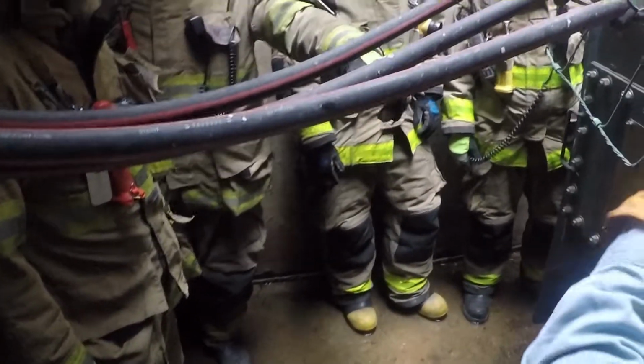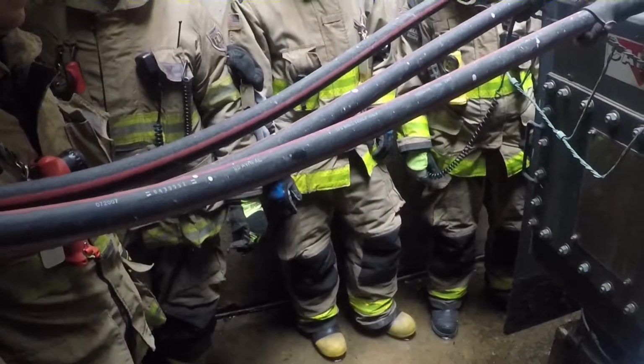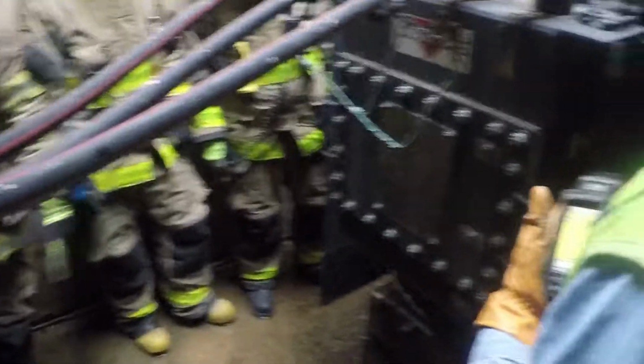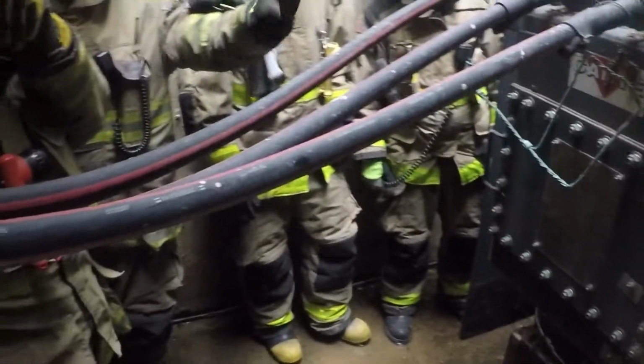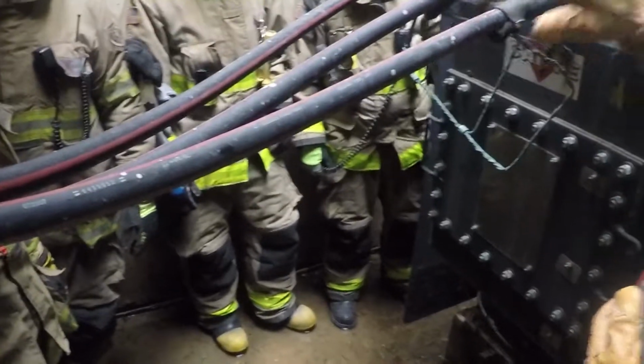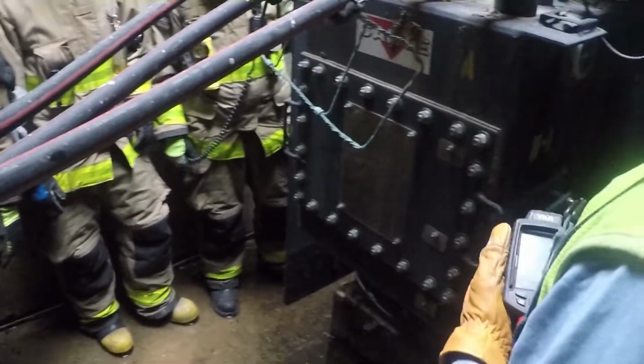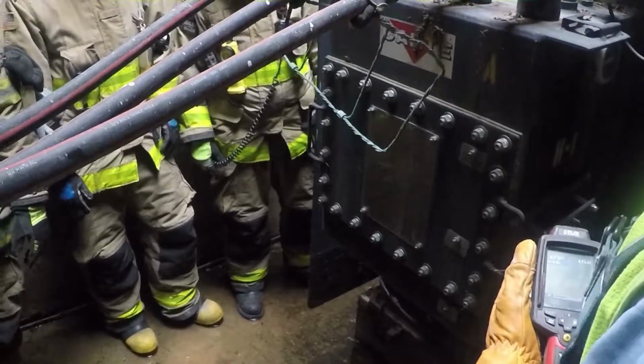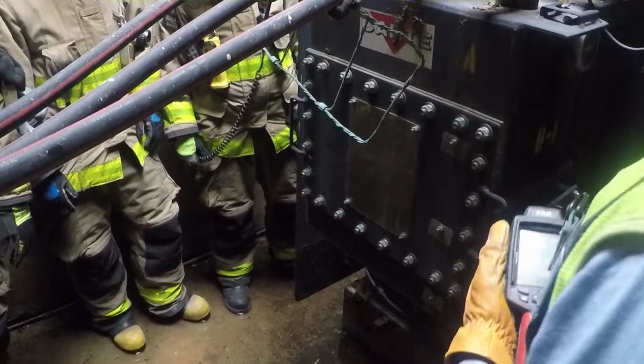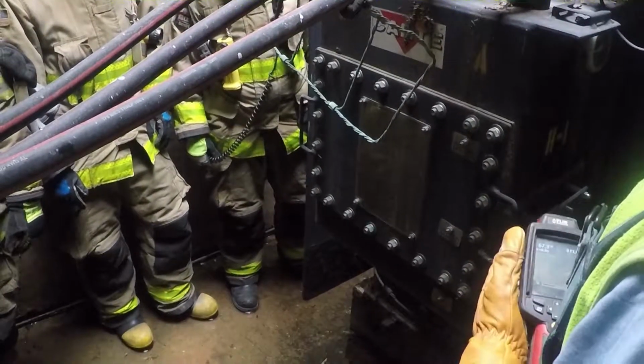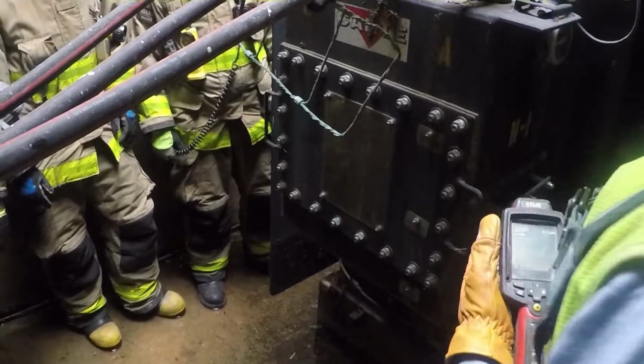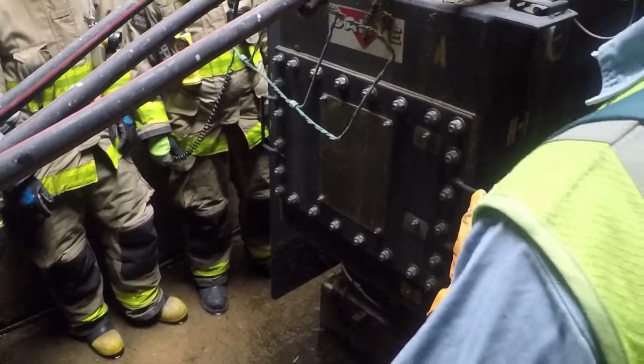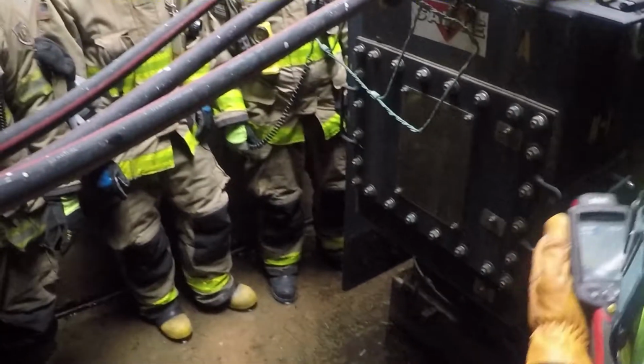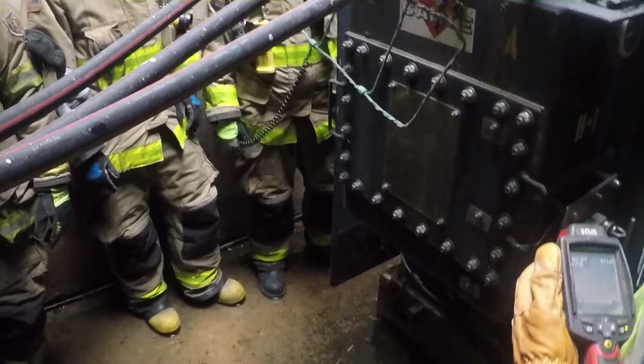But if we have an emergency down here, do we need to disconnect that from there? You shouldn't. If something were to happen, leave the primary intact and don't worry about it. You would never have to mess with any of this. If primary had some sort of fault, it would open at the station, and then if there was a fault, this would open up, and the protector would open up also, so it doesn't backfeed.